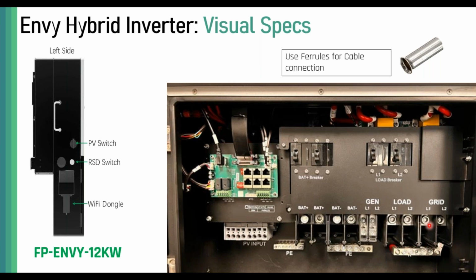And not to forget to mention, when hooking up a generator, this inverter can also do a two-wire start of the generator through these ports right here. They're normally open, normally closed ports. So we can hook up a 2-wire starter to the push button of the generator and hook it up to these ports right here, and then program your settings. So when the battery is at, let's say, a 20% state of charge, which is what we recommend for recharging for our 10-year warranty, cycling, depth of discharge, we recommend 20%. So we set it up to 20% and start the generator automatically.